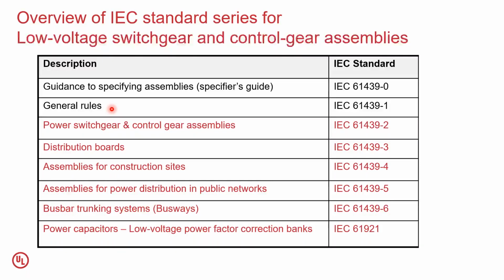So you might be wondering, what are these general rules? As you can see, the 61439 series consists of many different product categories. For example, for the panel boards, switchboards, MDBs, Part 2 is used. The title of the standard is Power Switchgear and Control Gear Assemblies, in short. And then you have the standard for distribution boards, which is more likely for unskilled people used in the buildings. Then you have the standard for assemblies for construction sites, the standard for assemblies for power distribution in public networks like the feeder pillars. Then you have the busbar trunking systems.